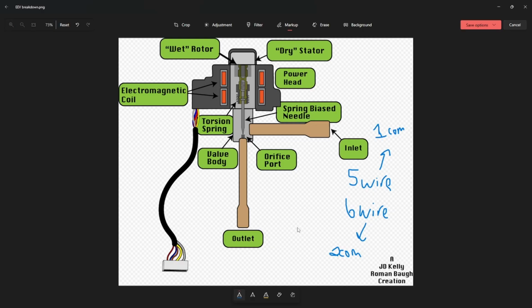And if you notice, the valve that's pictured has electromagnetic coils, you've got 4 of them. This is standard for most EEVs. You'll usually have 4 magnetic coils inside the valve body. They're not oriented in this way. They're oriented around the poles of the circular stepper motor. So for example, if you've got a circular stepper motor like this, it would be just like you'd see on a regular shaded pole motor.